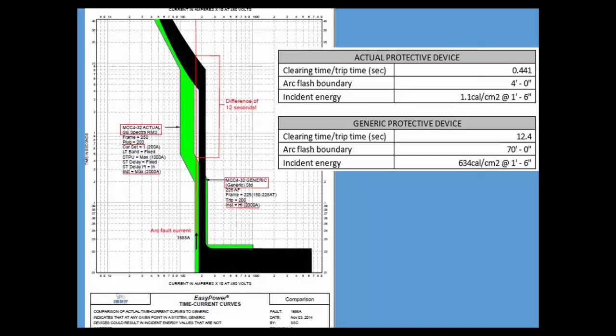In this case, it could actually be a huge advantage, because we go from something that is extreme danger above 40 calories to something that is actually below 1.2 calories, which could ultimately justify no arc-rated clothing. So there's a huge gap in some cases, and we want to make sure we get it right.